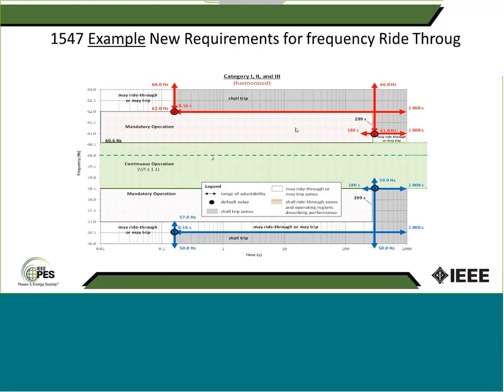So you see the green area is the continuous operation of DER for frequencies between 58.5 and 60.6 hertz. And then we have the mandatory operation with a limited trip time, basically, or duration. And also may ride-through, may trip, plus the shall trip regions. All right, so the 2 blue points, 1 and 2, and the red, these are also the default values, and the arrows show the range of adjustability.